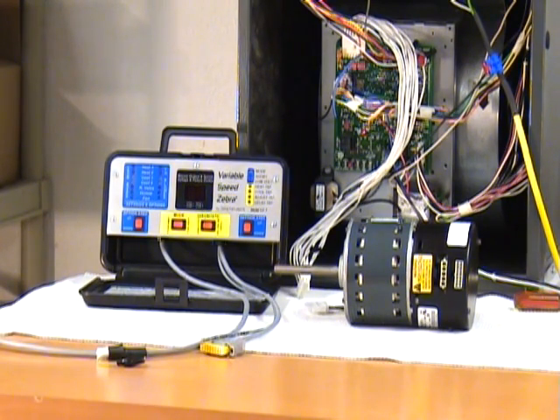And finally, the variable speed zebra makes a great comparative system analysis tool over time, enabling you to document the RPM, the energy required, to push a certain CFM through a system. If you document that system's values on initial installation, and you compare those values to new values that you might see when you do a spring or a fall checkup, you can spot trends that point to decreasing efficiency, or broken or open ductwork in attics or basements, or a system that might have too much of a restriction.